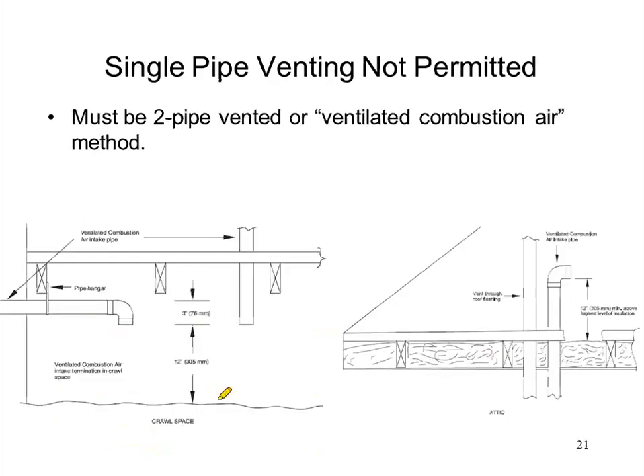These furnaces either need to be installed in a 2-pipe vented scenario, meaning I have 1 pipe from outside coming in with combustion air and 1 pipe leaving with the exhaust, or you can vent them with the ventilated combustion air method. What you cannot do is single pipe venting, which means you steal air from the room and exhaust out the exhaust pipe. So you either have to get the air directly from the outdoors or from a ventilated combustion air space. Those 2 types of spaces typically are the crawl space, like we're showing here, right?